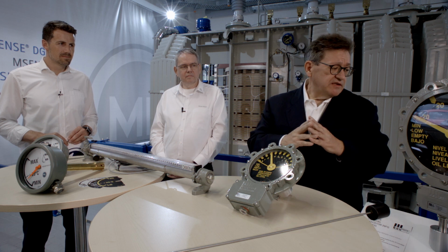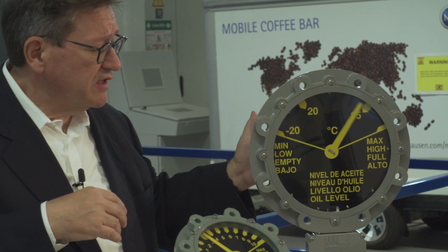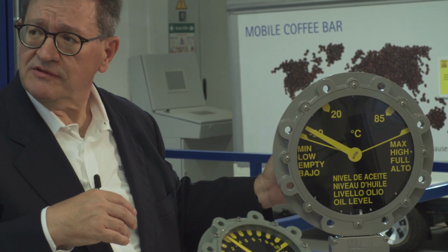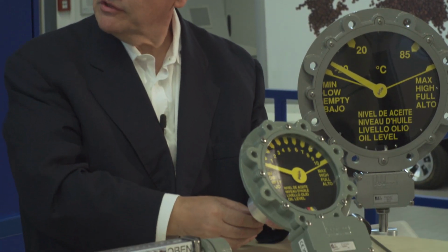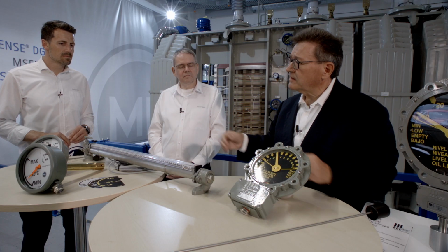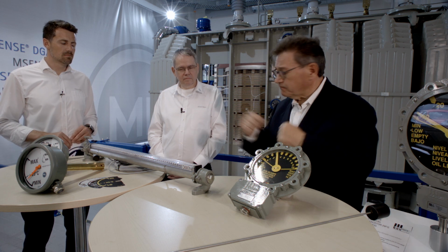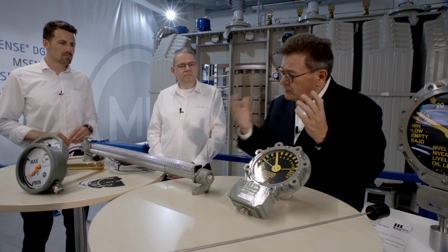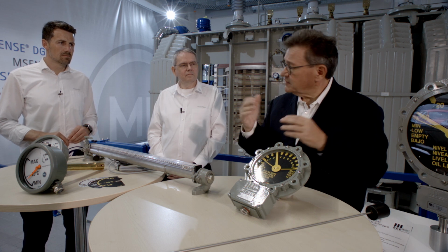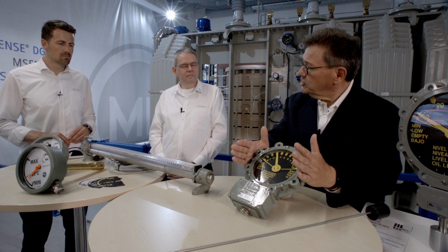Like for Messko, we have here two different types of moves. We have the radial moving of the arm, suitable for the OLTC conservator, and the axial moving of the arm, which is normally used in the conservators with the rubber bladder. The deviations are mainly recognizable by the dimensions and by the size and the form. Here we have three different sizes. We have 140 millimeters in terms of diameter of the flange, 220 and 320 millimeters.